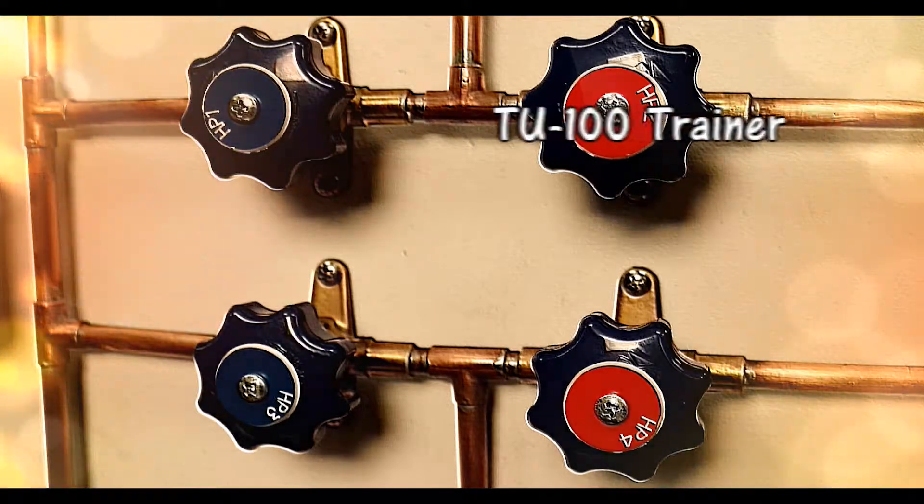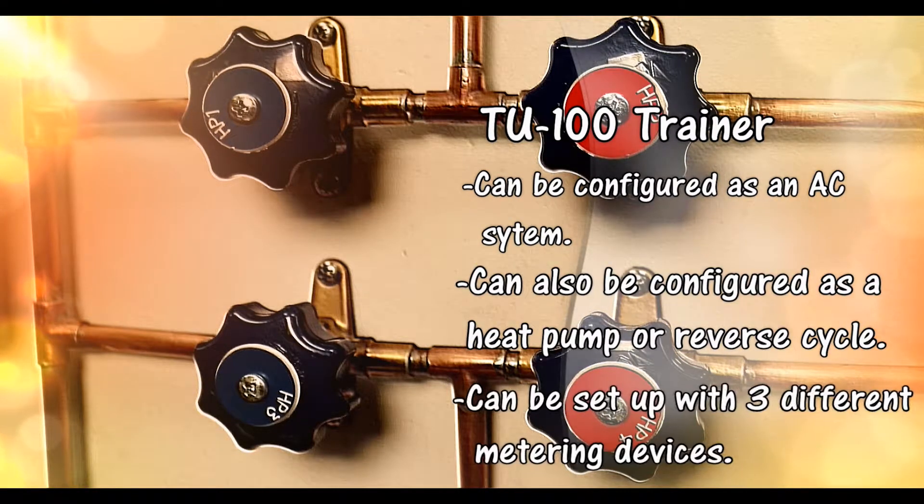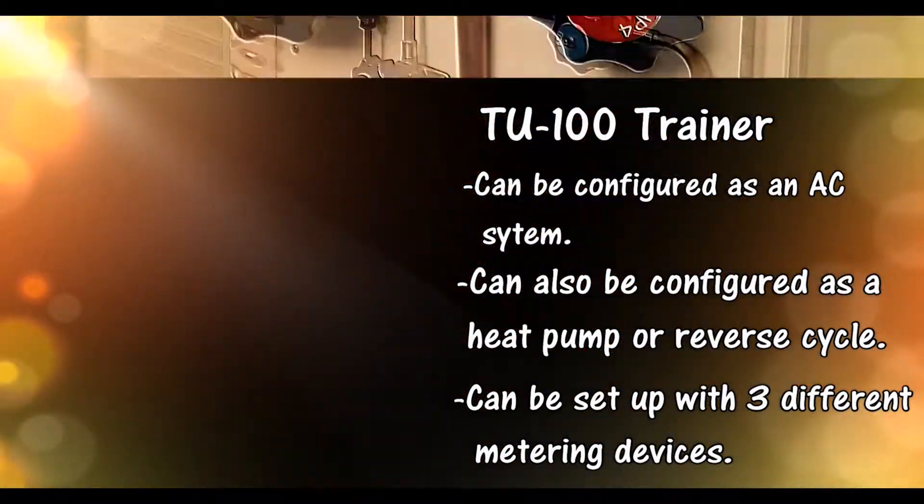When HP1 and HP4 are open, the upper coil functions as the evaporator and can be operated with one of three different metering devices. When HP2 and HP3 are open, the upper coil functions as the condenser.